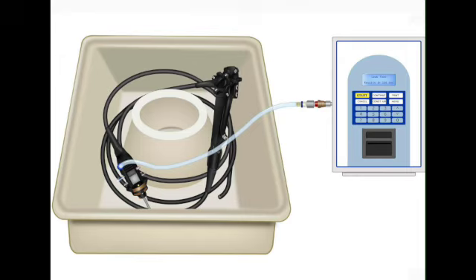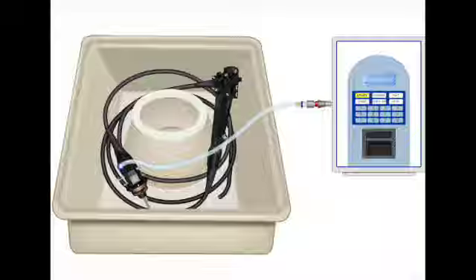Okay, and let's say it passes, no bubbles. How do you get it out of the water safely? Another critical moment. You have to keep the air pressure on while you take the scope out of the water. Keep it pressurized. Yes. You lift it out, dry it off, and only then do you release the pressure. If you release it while it's still underwater, the channels can create a vacuum and literally suck water back into the scope. Wow. It's like every single step has a potential pitfall.